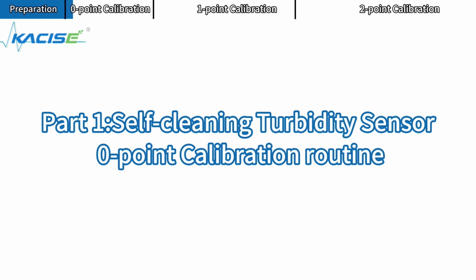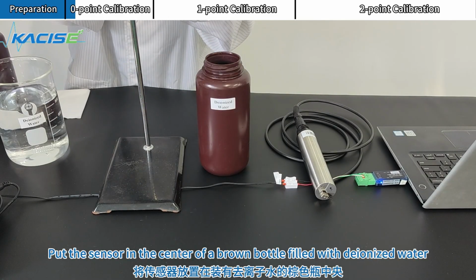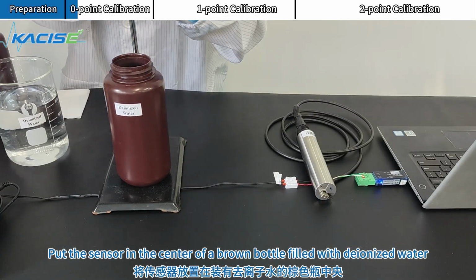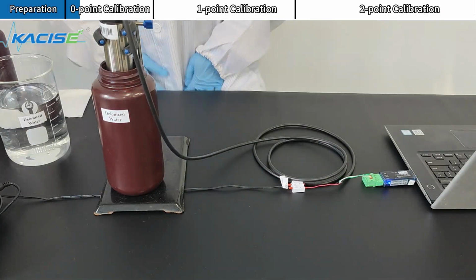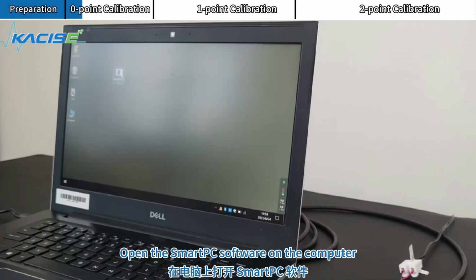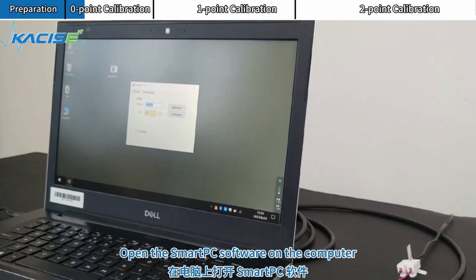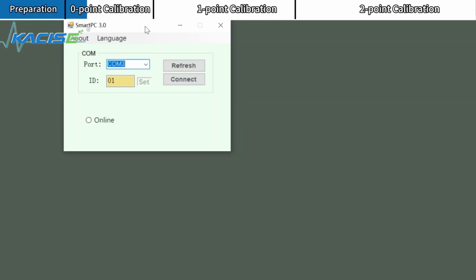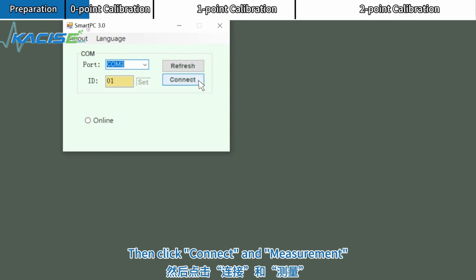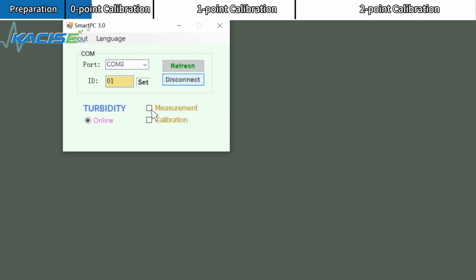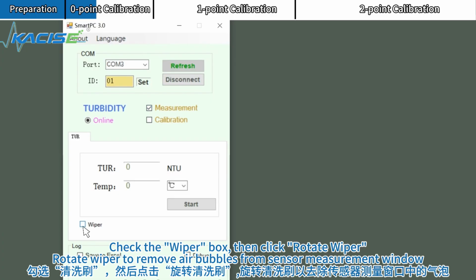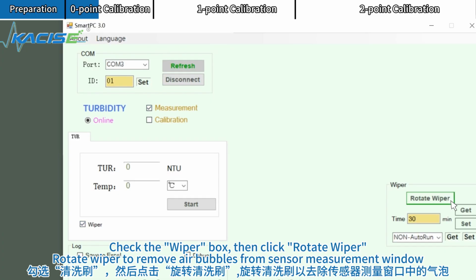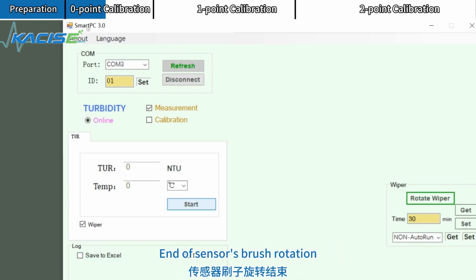0-point calibration routine. Put the sensor in the center of a brown bottle filled with deionized water. Open the Smart PC software on the computer. Then click Connect and Measurement. Check the wiper box, then click Rotate Wiper. Rotate wiper to remove air bubbles from sensor measurement window. End of sensor's brush rotation.